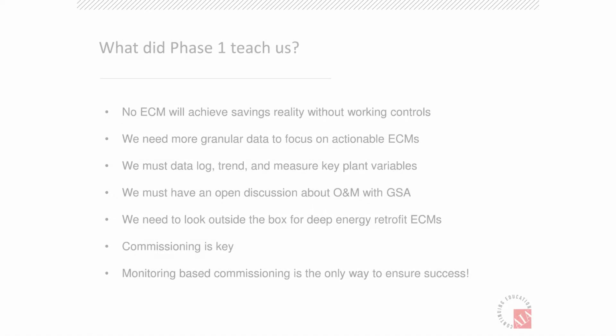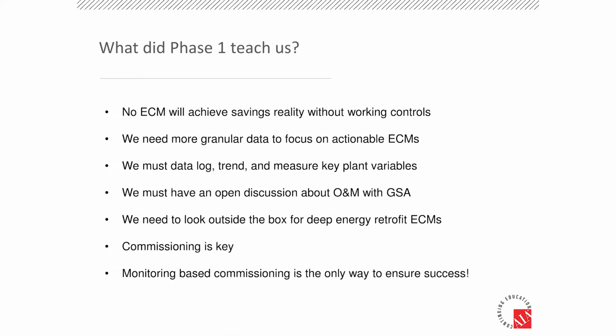We also realized that even with the central plant modifications we're doing in the now 5,000 or now 6,000 ton chiller plant in the 2 big buildings, we couldn't tell what was really going on until we got down to the granular data. And we were getting minute by minute data coming out of the control system.